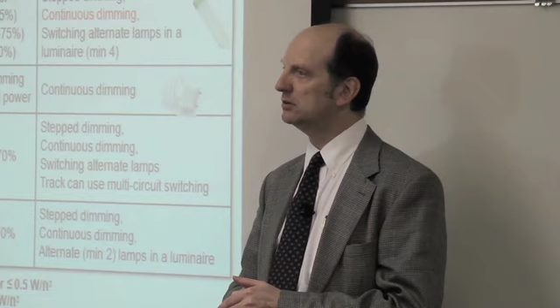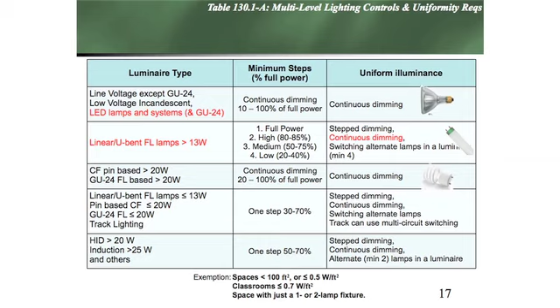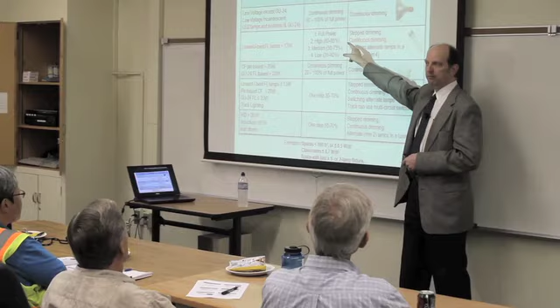If you're in a classroom, so it's got to be a classroom, it's not just other areas, you need to do dimming. You need to follow this requirement if you're above 0.7 watts instead of 0.5 watts. So one of the games for sure is going to be for folks to try to really get to low power wattage, to try to get those classrooms under 0.7, because if they do that, then they don't need to do dimming, and if they're using LEDs, they don't need to do dimming there.